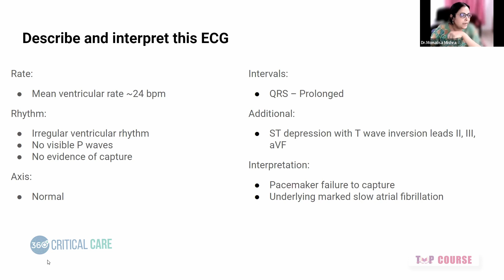So causes of pacemaker failure, they can ask you. Usually it can be a generator problem, like probably end of life or battery failure or any programming issue with the pacemaker, or over or under sensing. We all get to see these in our daily clinical practice. And then connection between the unit and patient, there could be some problem with the lead, like migration of the lead, fibrosis of the lead, malposition of the lead, or fracture of the lead.